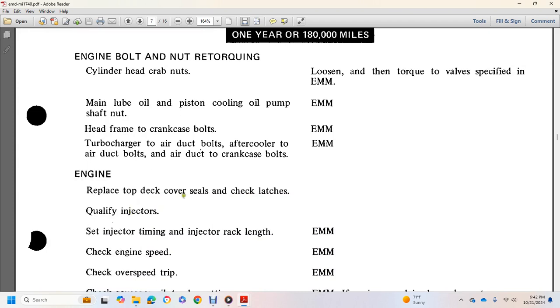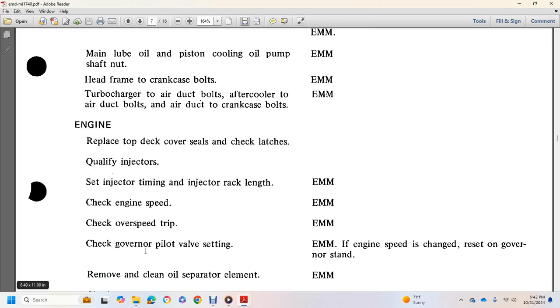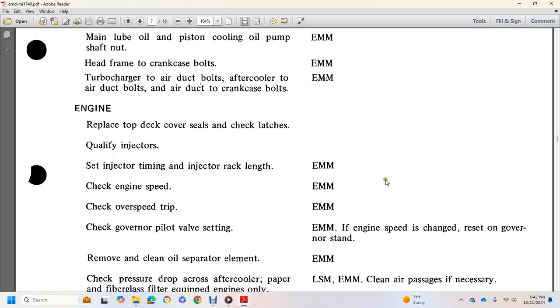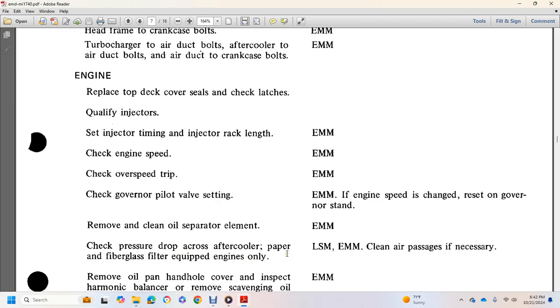Engine: check top deck covers and seals, and check latches. Qualify injector, set injector timing, injector rack, and check engine speed, overspeed trip, governor pilot valve setting. If the engine speed is changed, reset the governor stand. Remove and clean oil separating element. Engine maintenance manual: check the pressure drop across the aftercooler paper.